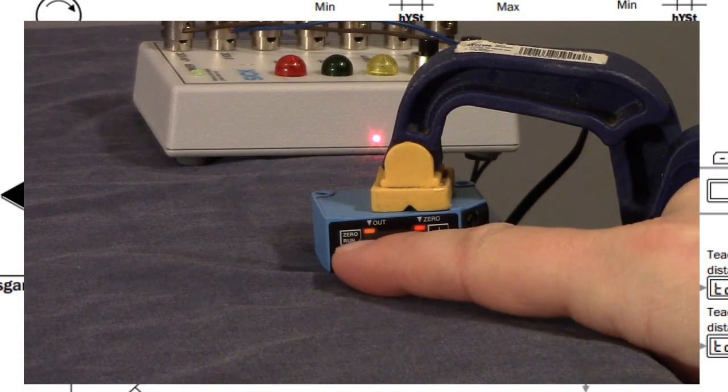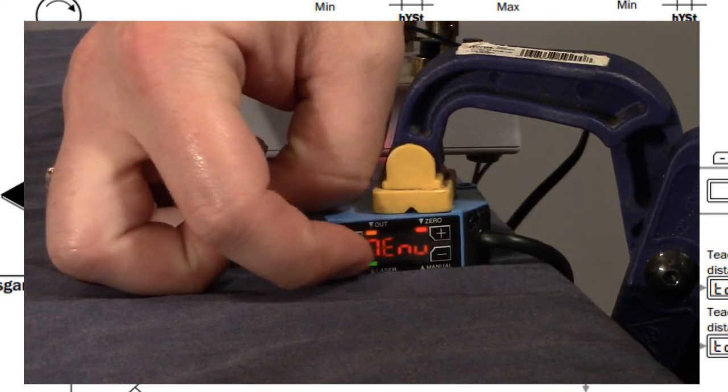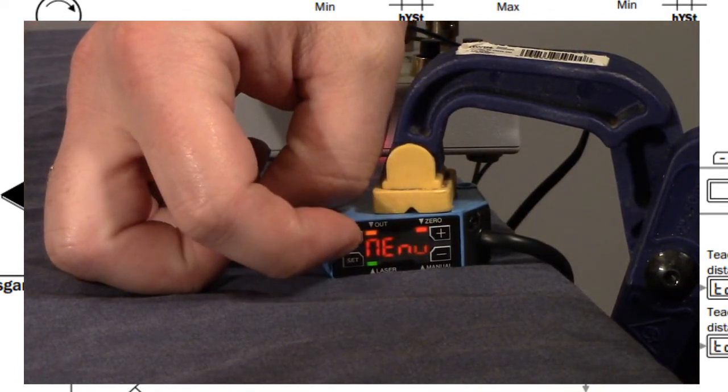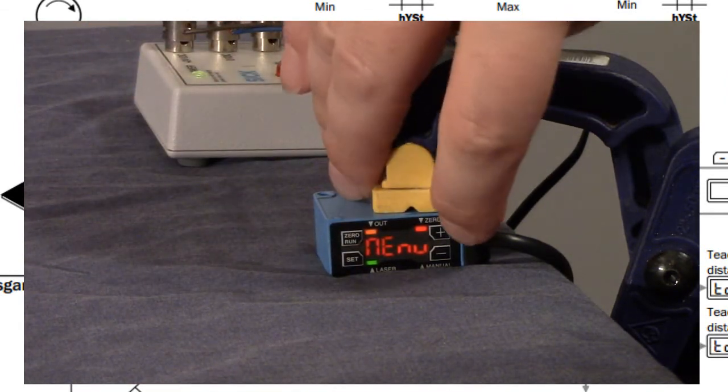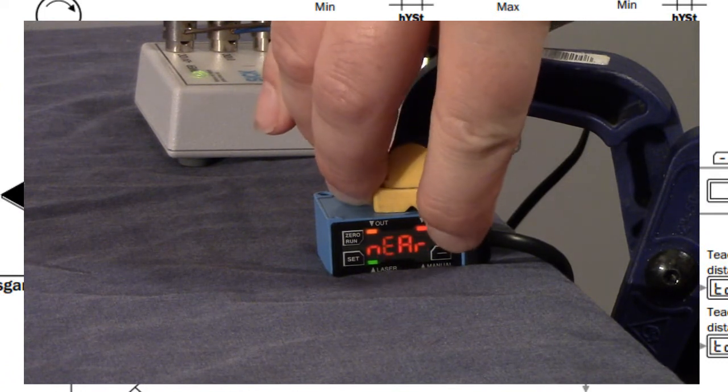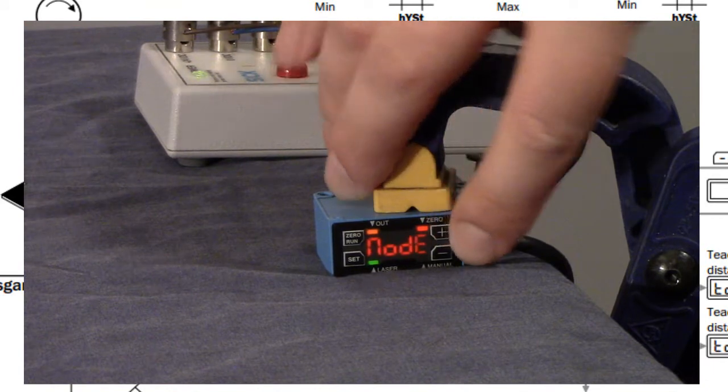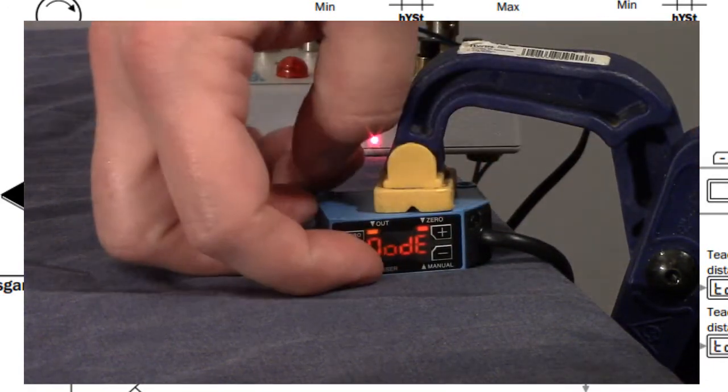Hit the run, the zero and run button and go back to run mode. And from that point forward, anything, any object that is closer than that taught distance will give you an output change. Anything further will change the output the other direction. And I'm very specific about being whether the output is on or off. Really later we can decide whether we want an active on or active off. That would be like a light operate, dark operate, normally open, normally close, whichever way you want to call it.